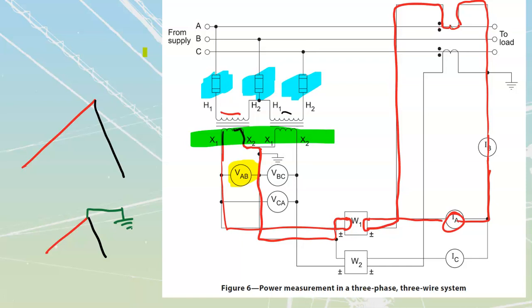This is just a corner grounded delta, and this is the first time we've been introduced to it inside of our units. It's still a delta system because across the middle I just have that ghost phase. I'm measuring this as my A to B, this is my B to C, and this is my C to A, measured across that one over there, done with this one over here. It's a corner grounded delta system that we have.